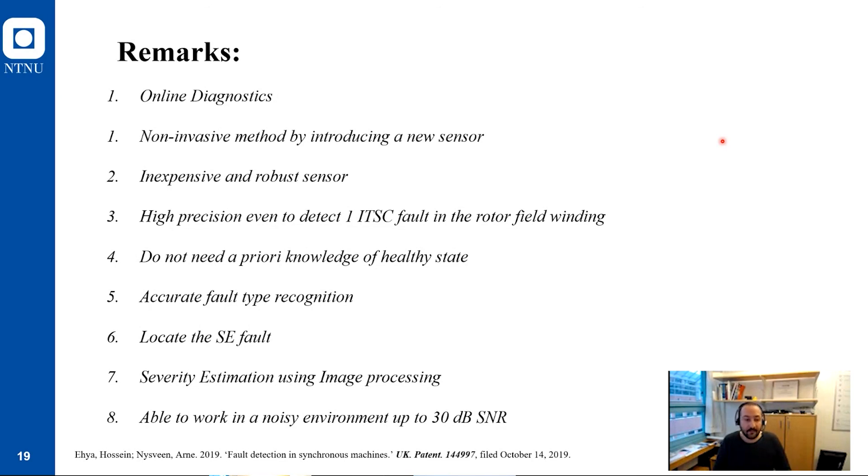For static eccentricity fault, we can also determine the location of the fault, in which direction we have a fault. We can also tell the operator that the severity of the fault is at which level, how long the machine can work in this status. The most important thing is the method is able to work in a real hydropower plant, even up to 30 decibel signal to noise ratio.